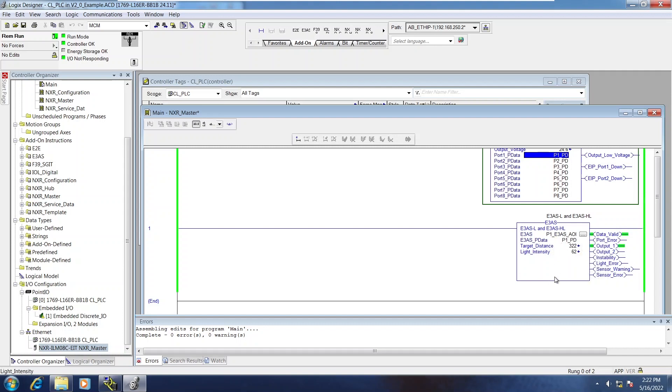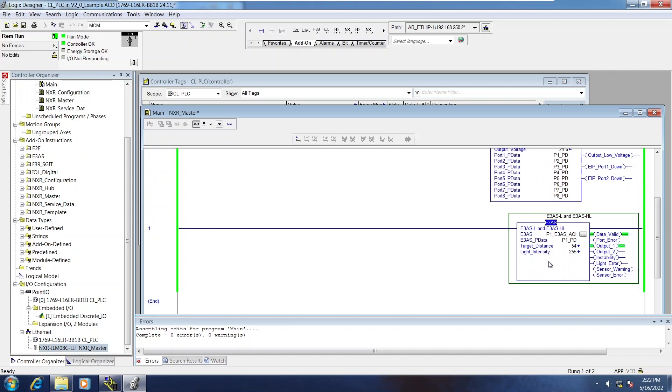So you can see the sensor itself, target distance is changing, the outputs are toggling. That's essentially an IODD file in an AOI. It knows what to do with the process data and all those status bits get passed across as well.